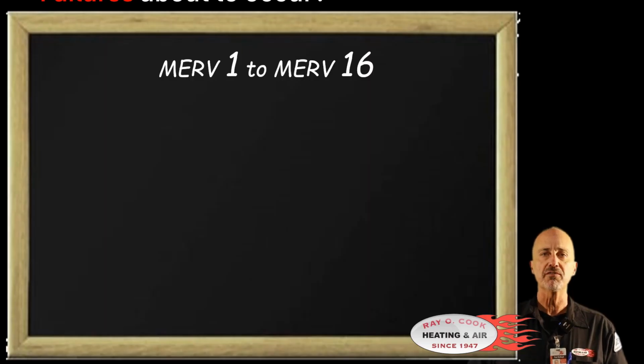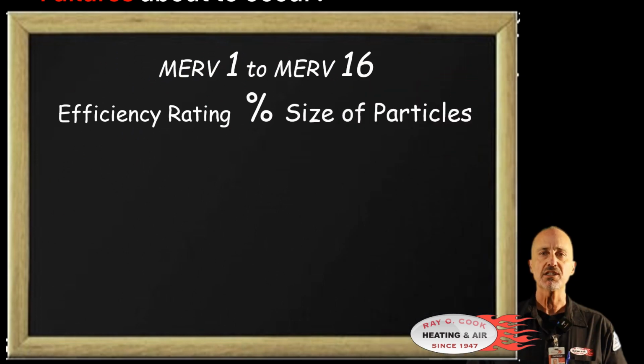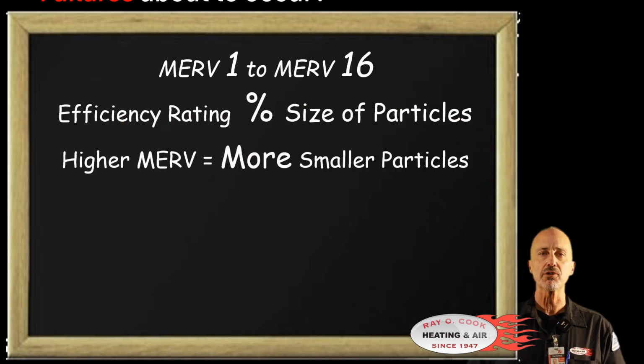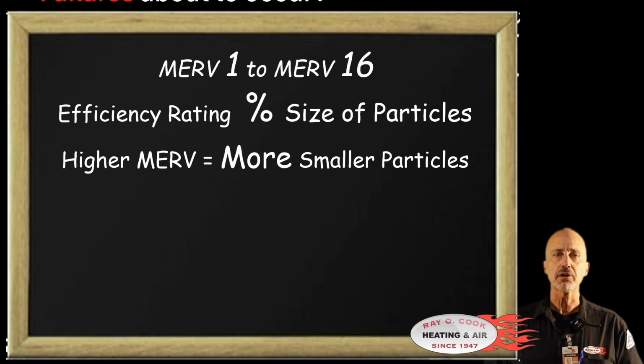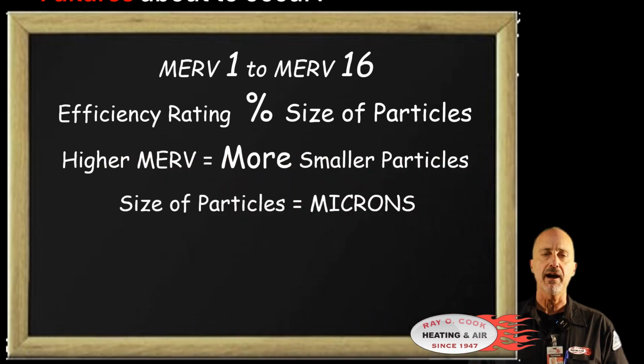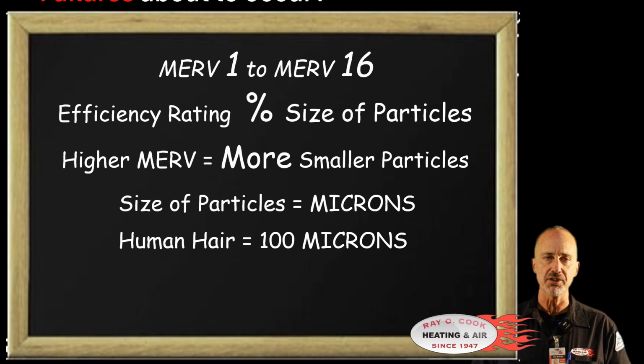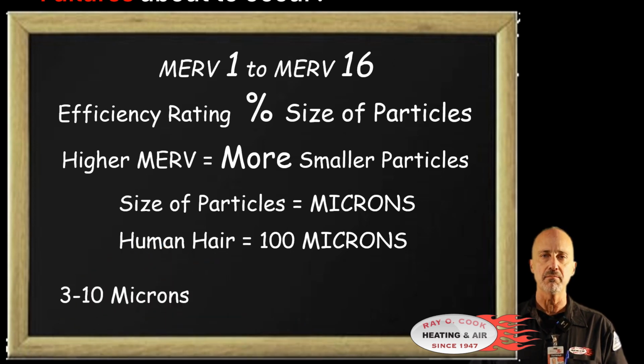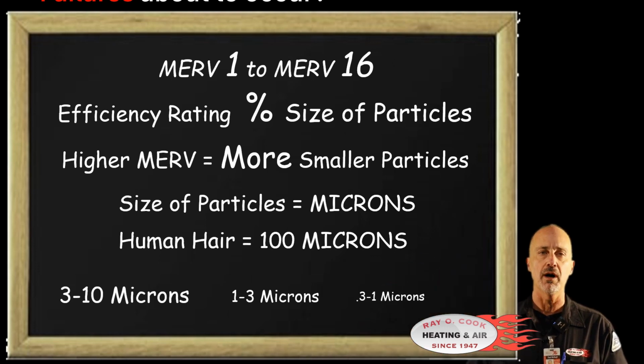The MERV scale will range from MERV 1 to MERV 16. It assigns an efficiency rating in percentage based on the size of particles the filter can capture. A higher MERV rated filter not only captures smaller sized particles, it captures more of those smaller particles. Particle size is based on microns. The average human hair is about 100 microns in diameter. The MERV rating is broken down into 3 groups: particles sized from 3 microns to 10 microns, particles 1 to 3 microns, and very small particles that are 0.3 to 1 micron in size.